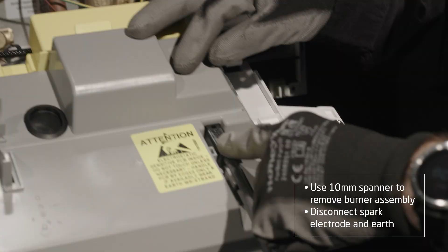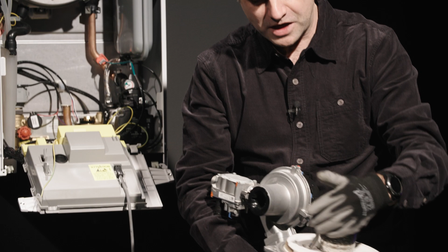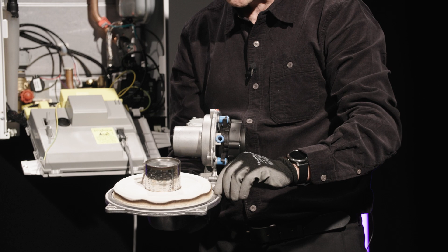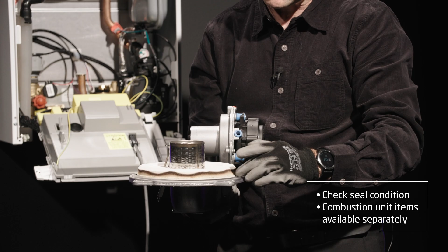So disconnect my spark electrode and my earth, and you can see on here the spark electrode is really retained in nicely there, so there's no worry of that falling out. Then I pull this out, and you can see it's a modular unit. I've got my burner and I've got my spark electrode and sensing electrode built into one there, and I've got this seal here. There's no need to change that seal on a service. If you're inspecting it, you just make sure it's in good condition, make sure it's not flaking off or going brittle, and you can reuse it.